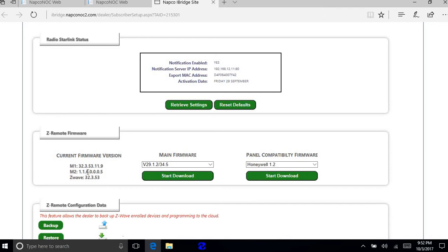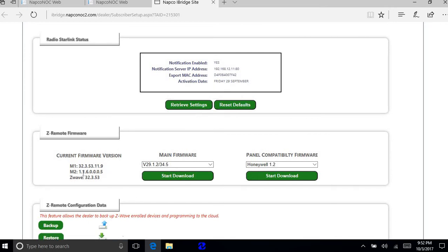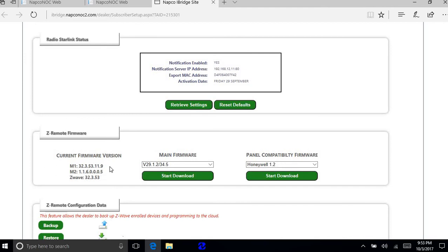And if it says zeros in here, then you're going to have to retrieve settings again until you see the firmware file. If it sees zeros, it's going to think it's a Napco panel. So that's a very important file.